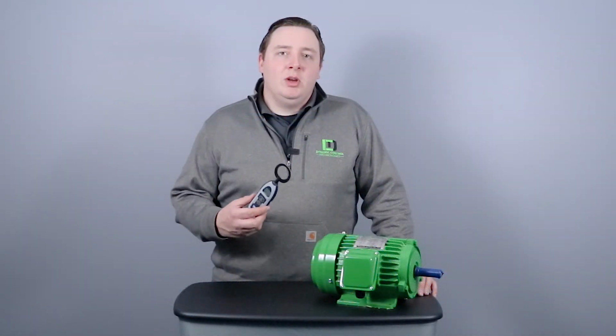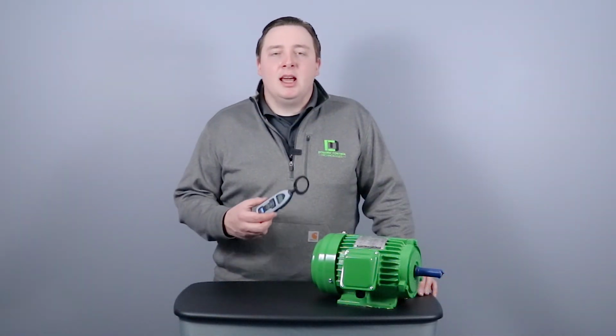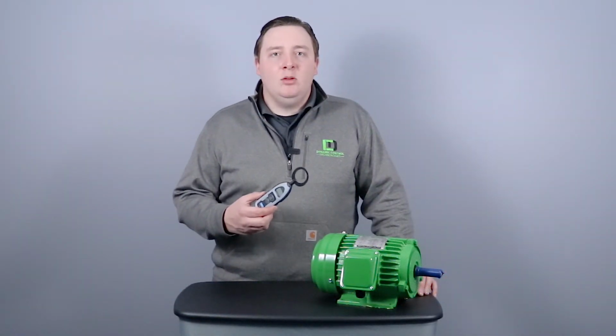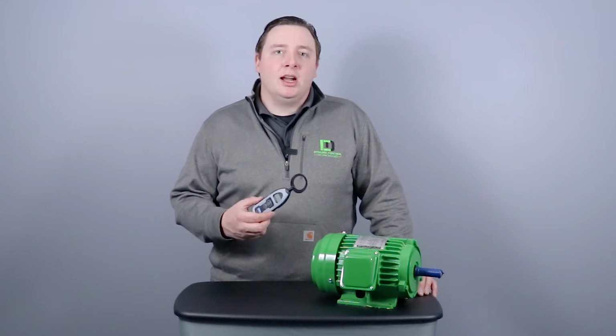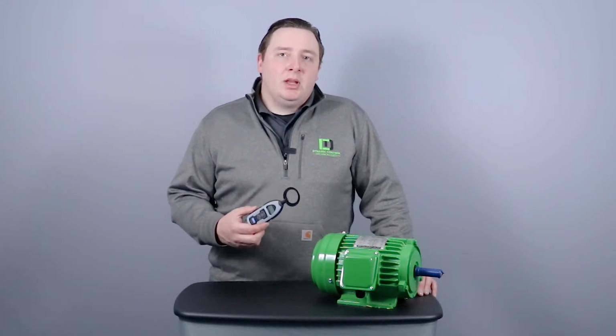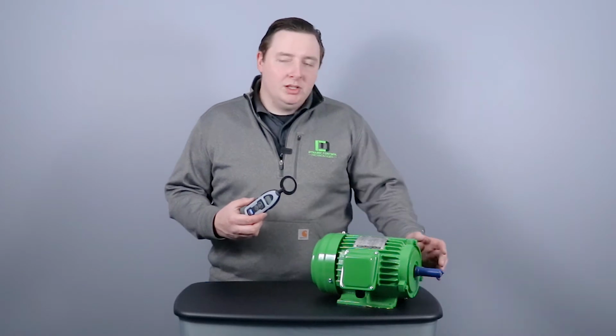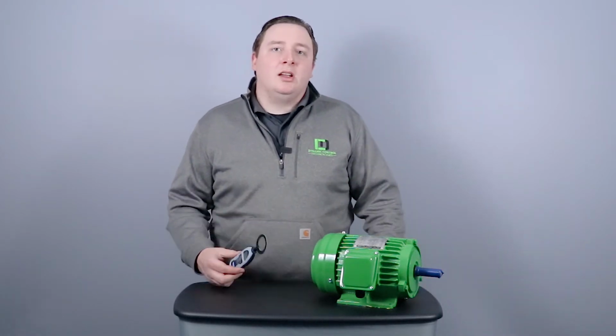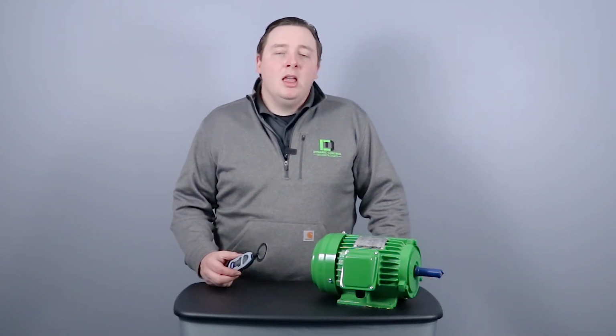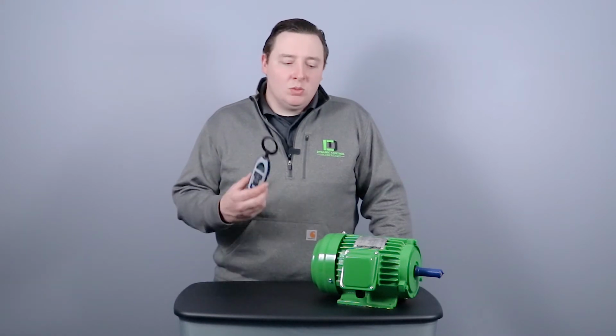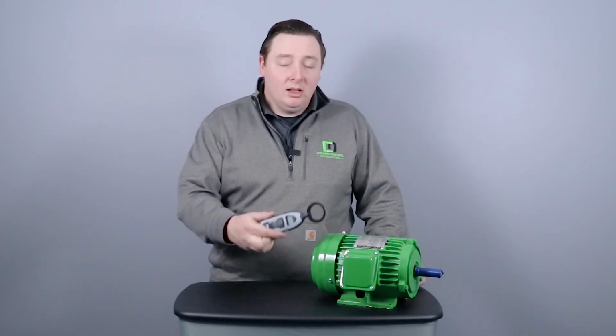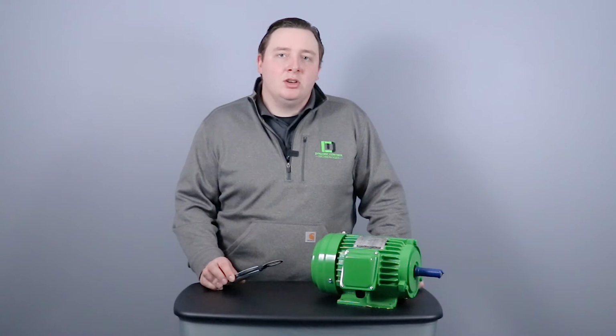One of the other tools that we carry on every truck here at Dynamic is an SKF TKED1 electrical discharge detector pen. Customers sometimes have concerns about shaft voltages that ground through the bearings that can cause premature motor failure and bearing failure. However, with this wand, we're able to non-contact detect whether or not those discharges are even present.